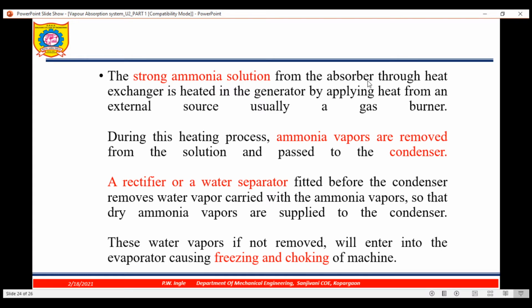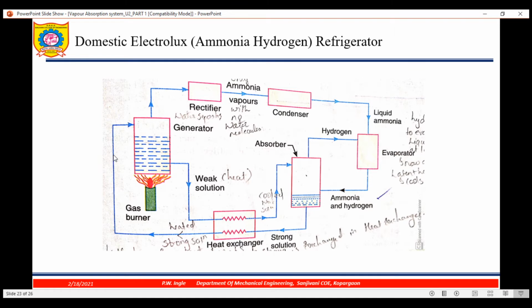The strong ammonia solution from the absorber, through the heat exchanger, is heated in the generator by applying heat from an external source, usually a gas burner. So here the strong solution enters the generator. The strong solution consists of ammonia and water: water as an absorbent and ammonia as a refrigerant. Now ammonia will get separated out. The vapor ammonia goes to the rectifier. The rectifier is used to remove whatever water particles may be carried away by the ammonia vapor, and they are fed back to the generator.